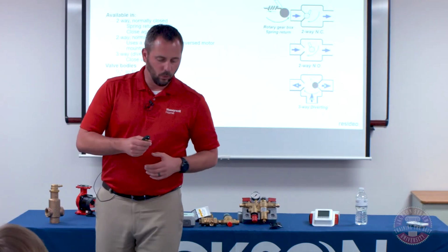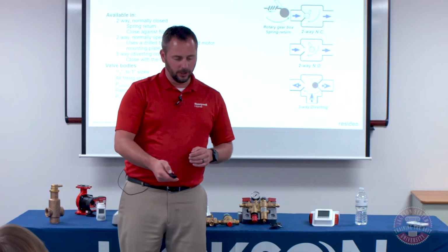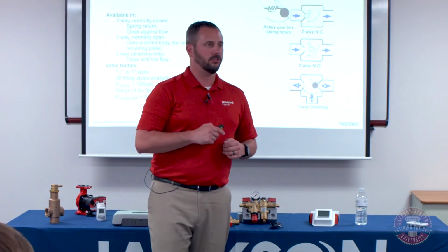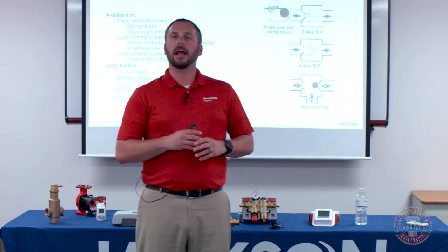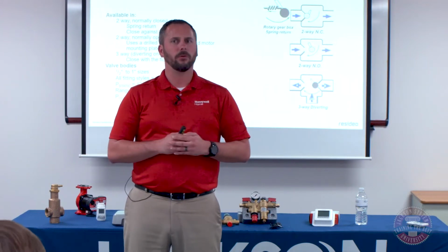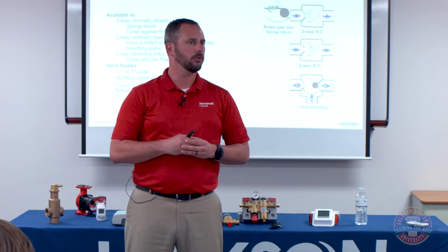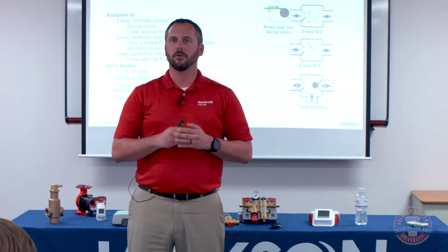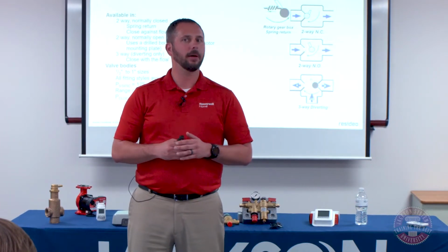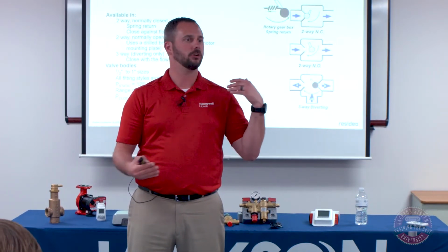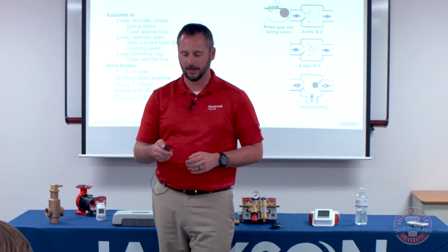How do I have my slides arranged here? I'm going to talk about coefficients of velocity. I get asked a decent amount for 1 1/4 and larger zone valves. Most of the time, they're not needed, and I'll talk about that based on close-off pressures and flow rates in just a second.